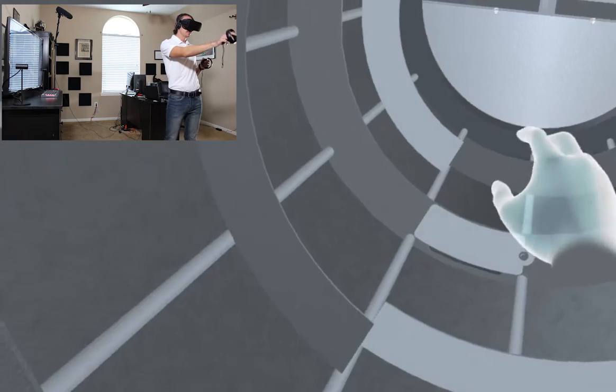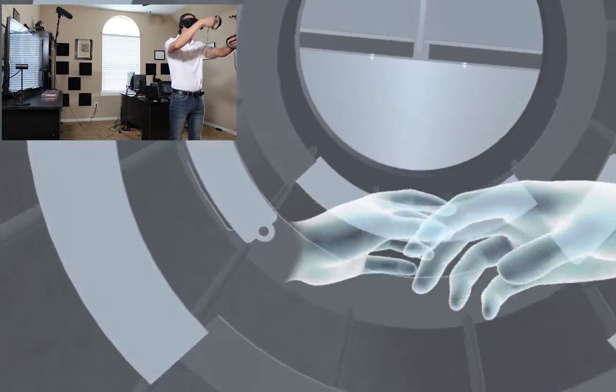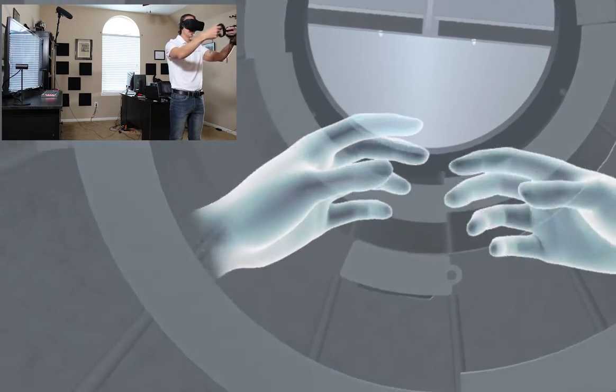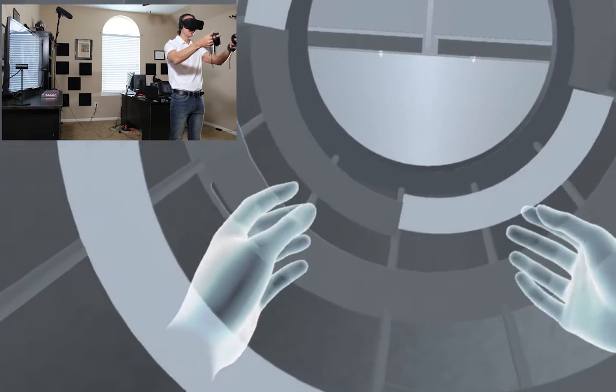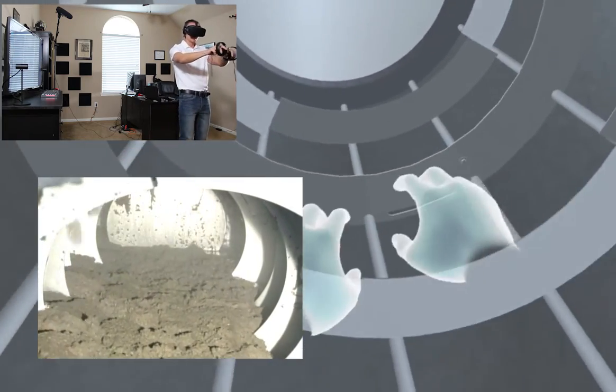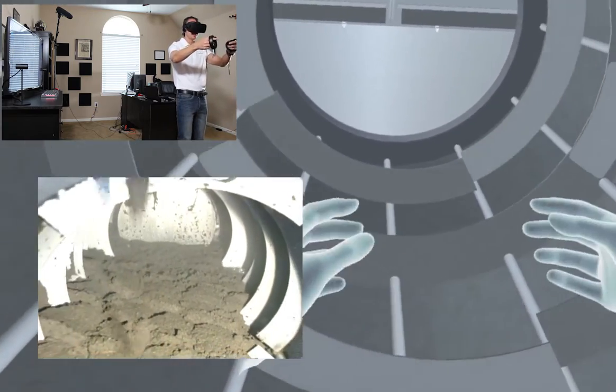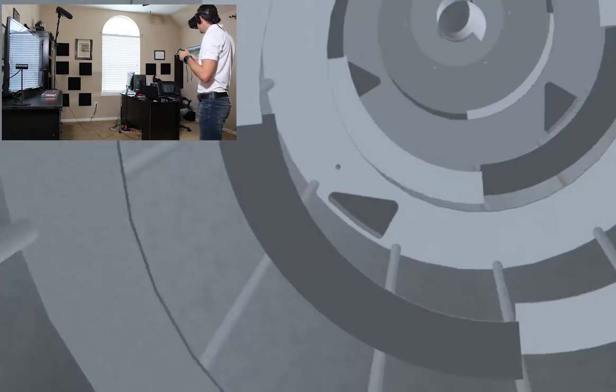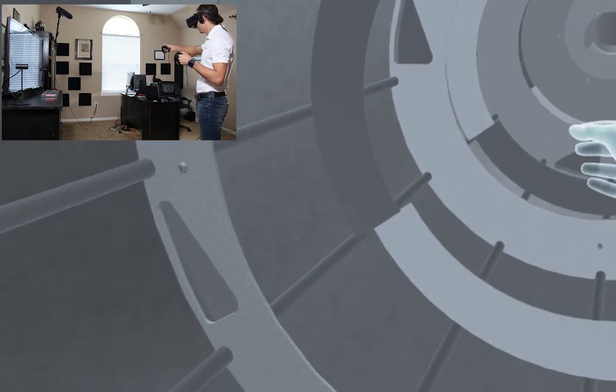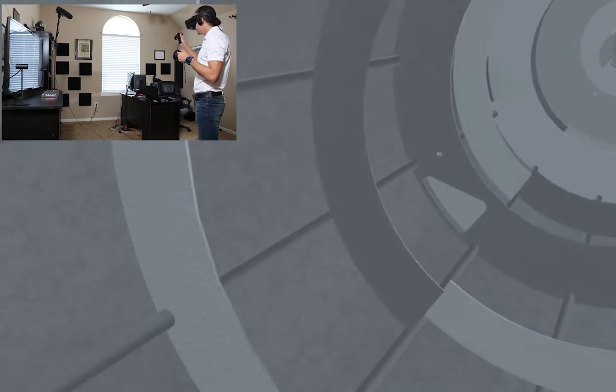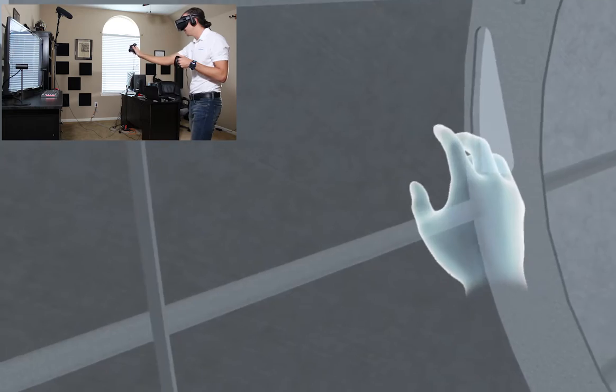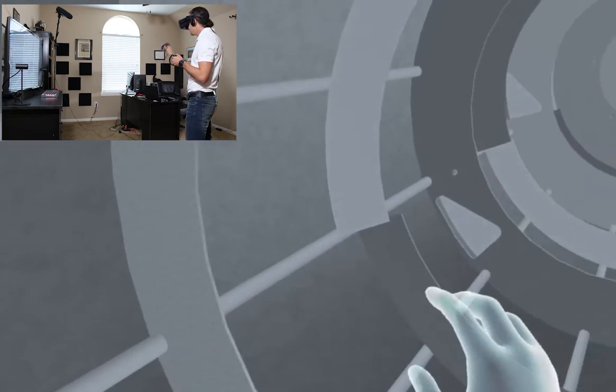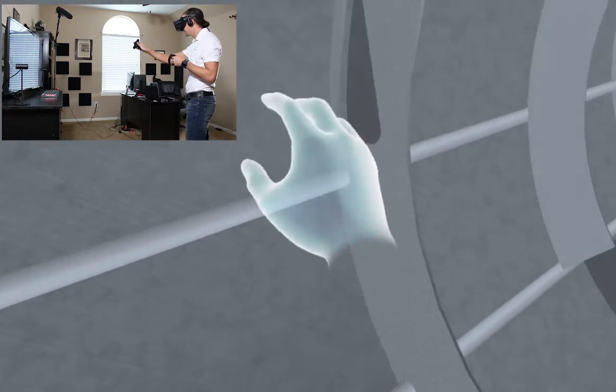Now, the other thing that these split augers do is they get the sludge to flip over each one of them. So we're not allowing any sludge bypass. When this RDT is in operation, or any RDT is in operation, you have a decent amount of sludge really filling up the bottom of this drum. It's almost like a semi-filled pipe. So if you allow the sludge to just go through an empty RDT, you're going to have a lot of bypassing.